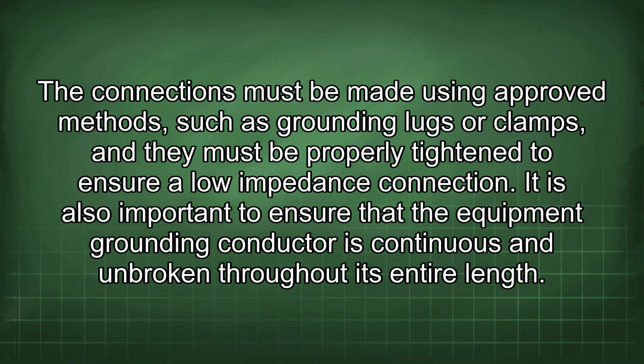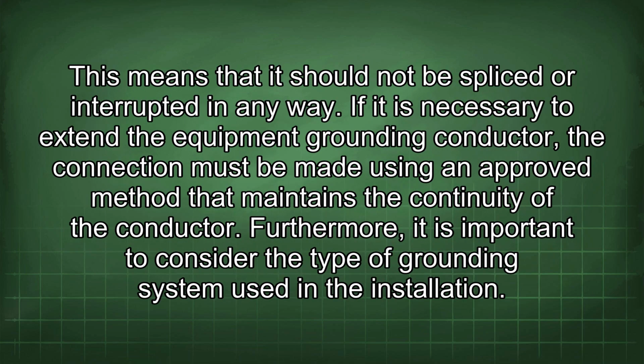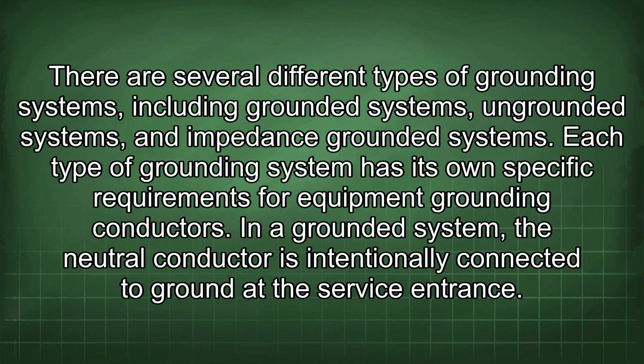It is also important to ensure that the equipment grounding conductor is continuous and unbroken throughout its entire length. This means that it should not be spliced or interrupted in any way. If it is necessary to extend the equipment grounding conductor, the connection must be made using an approved method that maintains the continuity of the conductor. Furthermore, it is important to consider the type of grounding system used in the installation. There are several different types of grounding systems, including grounded systems, ungrounded systems, and impedance grounded systems. Each type of grounding system has its own specific requirements for equipment grounding conductors.